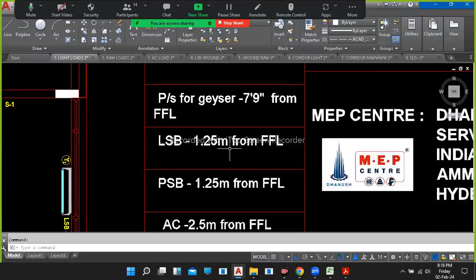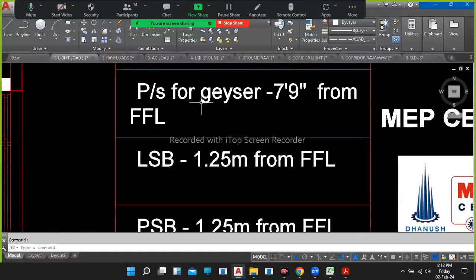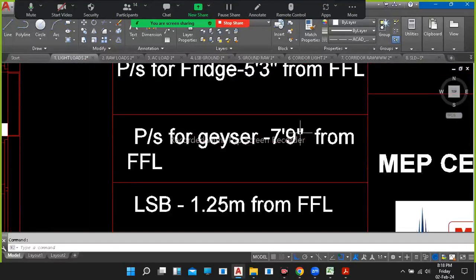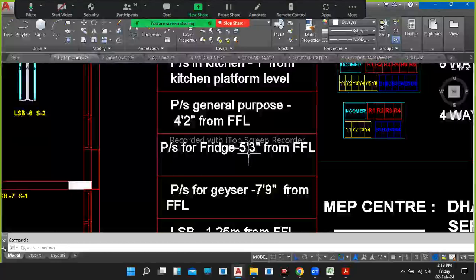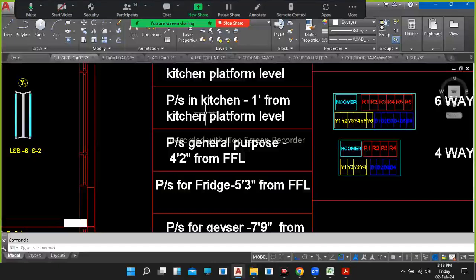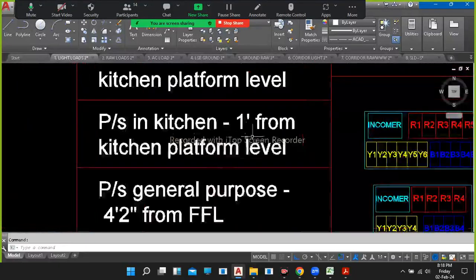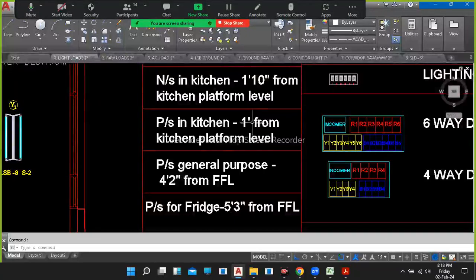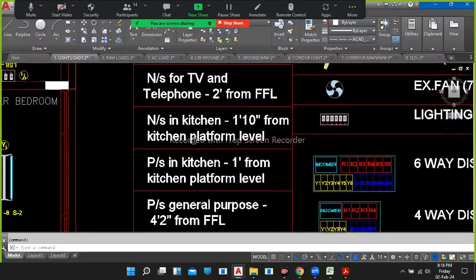LSB 1.25 meter from finished floor level. For geyser, 7 feet 9 inches from finished floor level. For fridge, 5 feet 3 inches. For general purpose, 4 feet 2 inches. In the kitchen, we provide power sockets from the kitchen platform level or KCL, kitchen counter level, 1 feet from the kitchen counter level. Normal sockets in the kitchen if you want normal sockets.